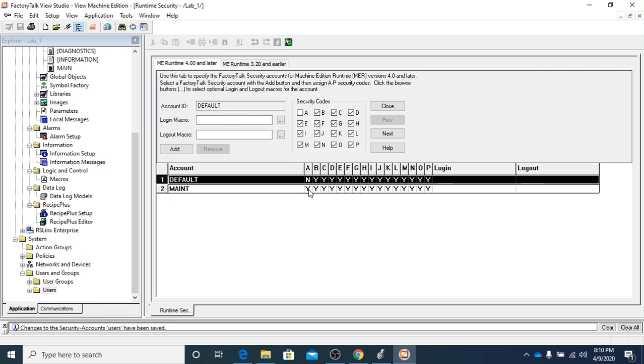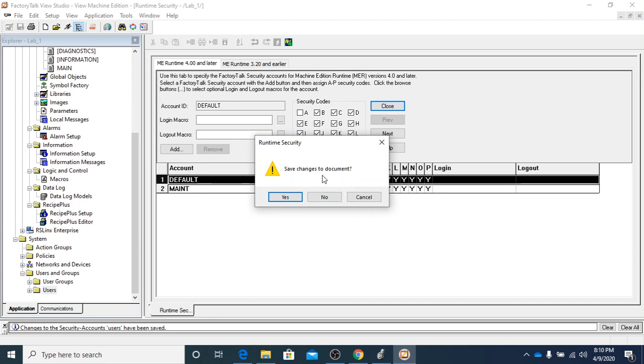The MAINT has yeses on everything, so no matter what screen you're on, they have access to all those. Since we've got this updated and hit the accept button, we have no more changes to make. Now we want to close, and it's going to say save changes to document. You want to save these changes or they will not take. If you hit no, it will put it back to just the way it was when we first came into the page. So if you made a mistake and don't know what you made a mistake on, you can hit no and it's going to set everything back. But I feel pretty good about what we've done, so I'm going to click yes. That's going to close that window — now we have our runtime security tab populated with the information we need.